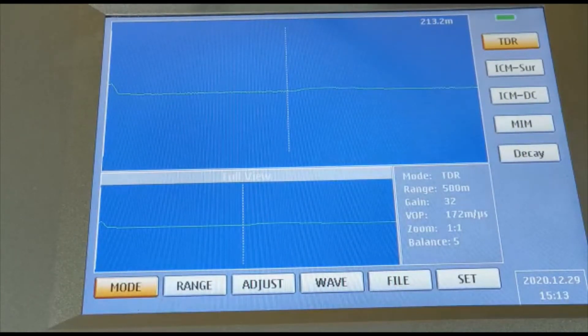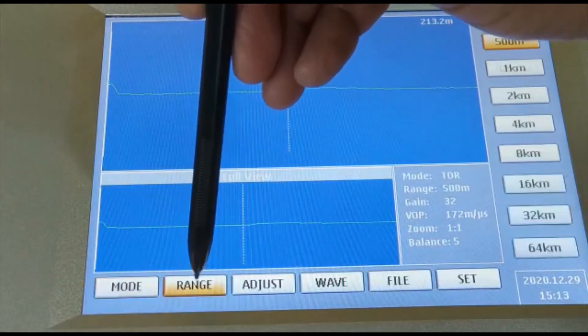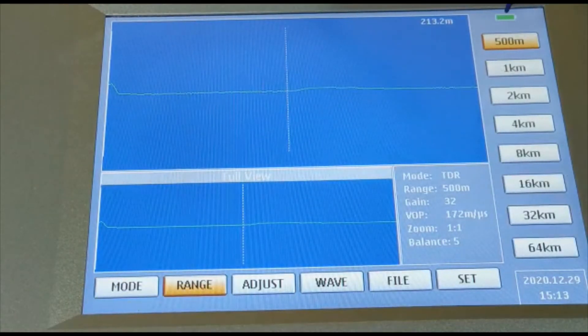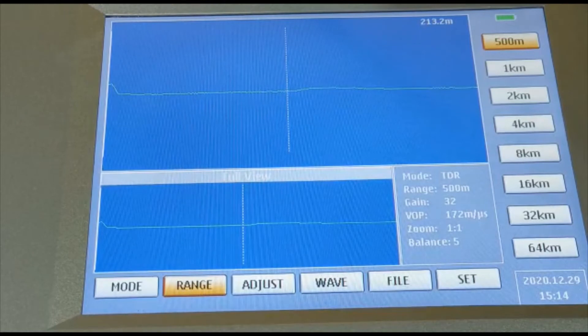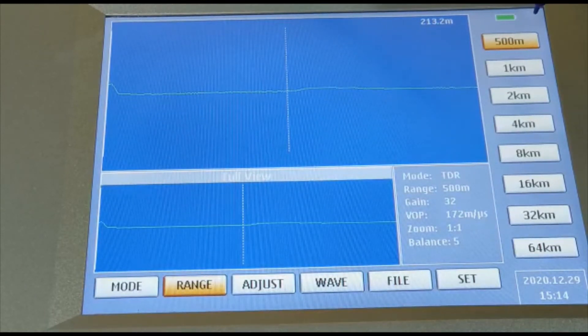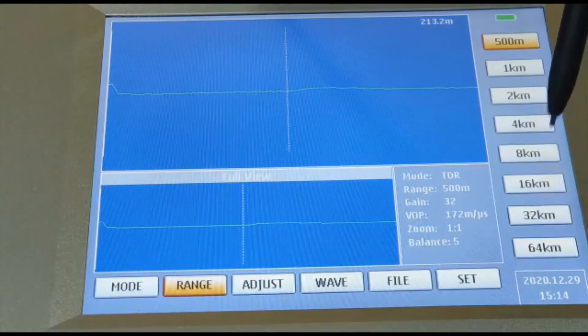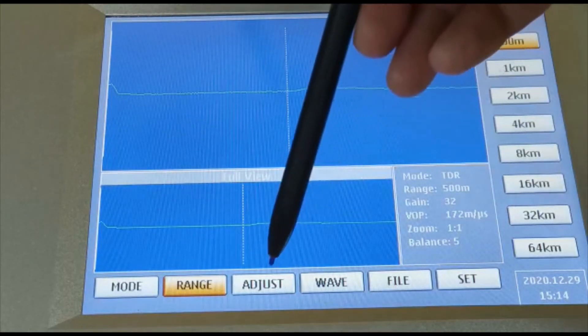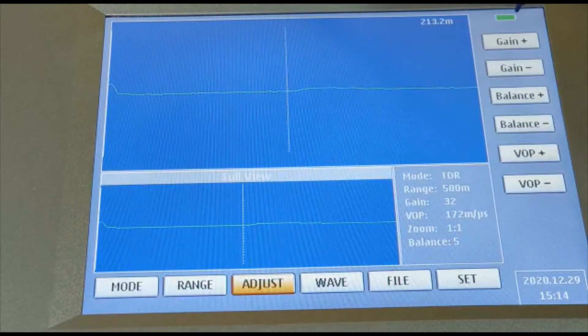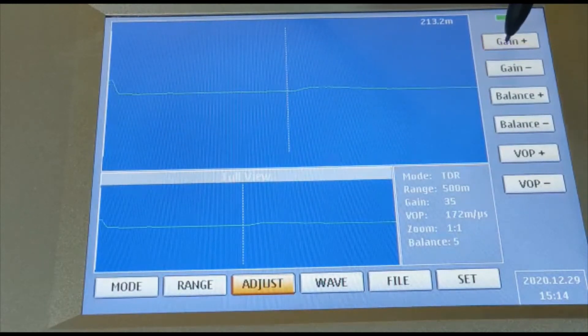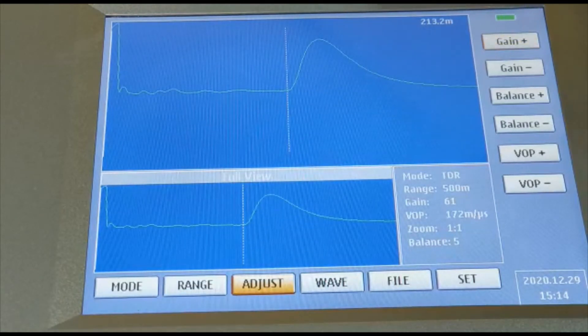If you go to the range option, you can see that the equipment has different ranges for different cable lengths. You can select based on the cable length, whether it is 500 meters, 1 kilometer, 2, 4, 8, 16, 32, or 64 kilometers. Go to adjust and you can see that you can adjust different gains — increase or decrease — so that you can see the clear distance to fault.